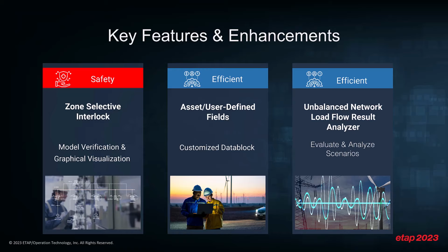ETAP Unbalanced Load Flow Result Analyzer is a time-saving tool that compares and analyzes multiple unbalanced power flow reports in a single consolidated tabular view. You can compare the results of the general information about a project or more specific information such as the unbalanced load flow results for buses, branches, loads, sources, and of course it gives you insight into the impact of various what-if scenarios in one glance, allowing you to choose the best outcome for your power system.